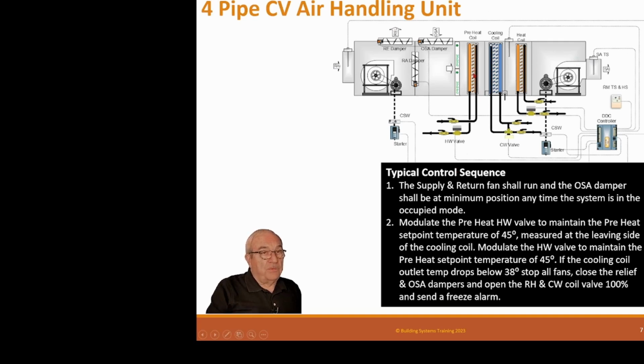So these preheat coils are designed for areas that have very low temperature, and it does two things. Not only does it preheat the air and keep things from freezing up, it also helps this heating coil.